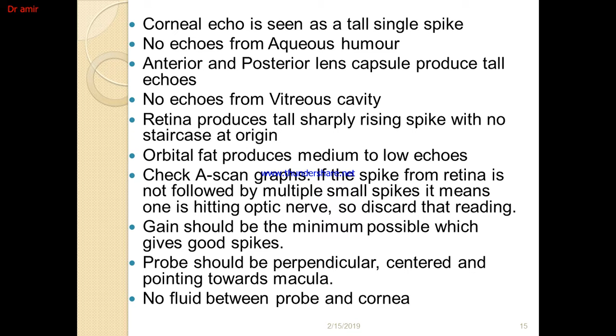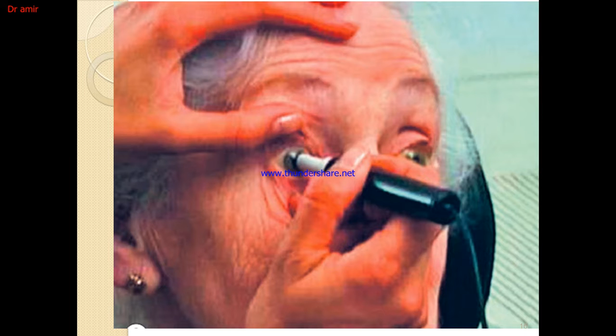If the spike from the retina is not followed by multiple small spikes, it means the probe is hitting the optic nerve, so discard the reading. Also, the gain should be the minimum possible which gives a good spike. And the probe should be perpendicular, centered and pointing to the macula. This is also important for proper axial length measurement. And there should be no fluid between the cornea and the probe.